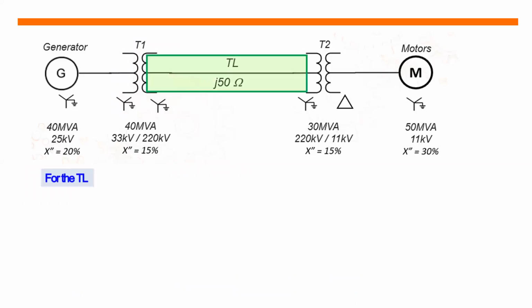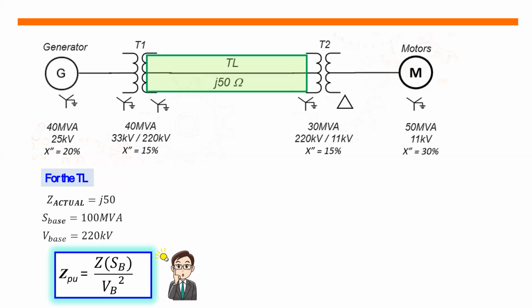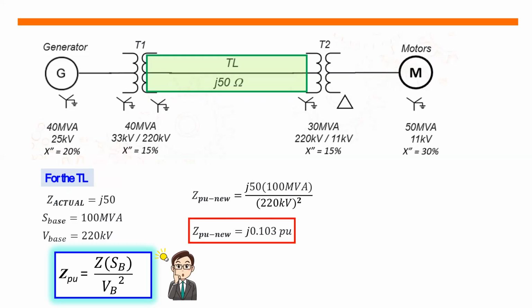Now, for the transmission line, the actual impedance is equal to j50 ohms. The base power is still 100 MVA. The base voltage is equal to 220 kilovolts. So using our equation for the per unit impedance, we will just substitute all the given values. Then the new per unit impedance for the transmission line is equal to j0.103 per unit.